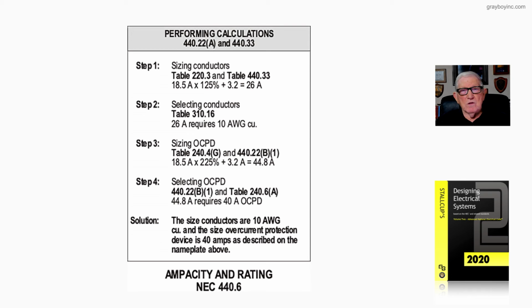90.4 situation, the authority having jurisdiction based upon the location in the country where the unit is installed would give you these values. But always remember that 110.3B of the code does say that the nameplate, the manufacturer's instructions must be followed, so usually your authority doesn't have any problem with what I've just quoted to you.